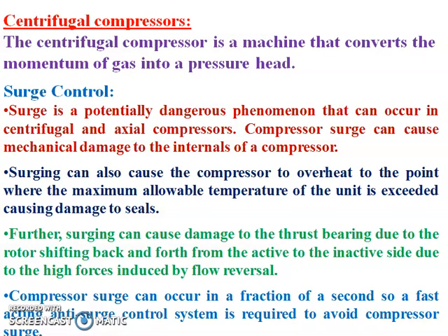The centrifugal compressor is a machine that converts the momentum of gas into a pressure head. And in a centrifugal compressor, the important controller is the surge control. Surge is a potentially dangerous phenomenon that can occur in centrifugal and axial compressors. Compressor surge can cause mechanical damage to the internals of the compressor. The surging can also cause the compressor to overheat to the point where the maximum allowable temperature of the unit is exceeded, causing damage to the seal.